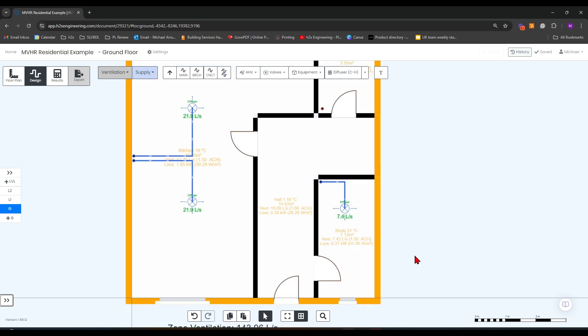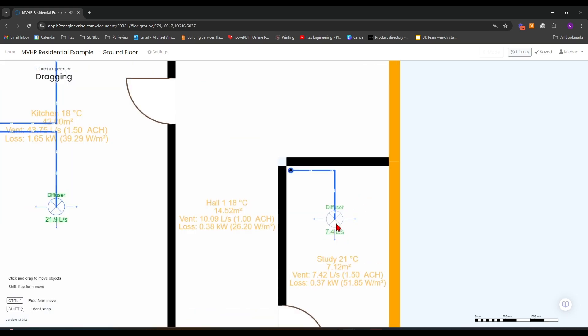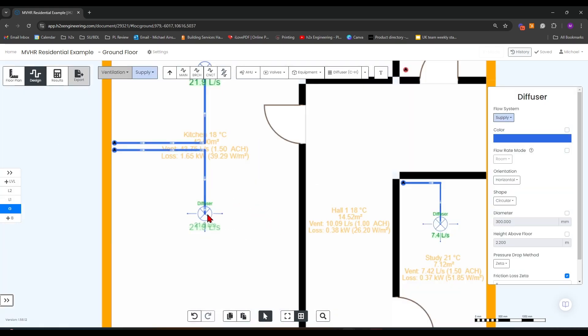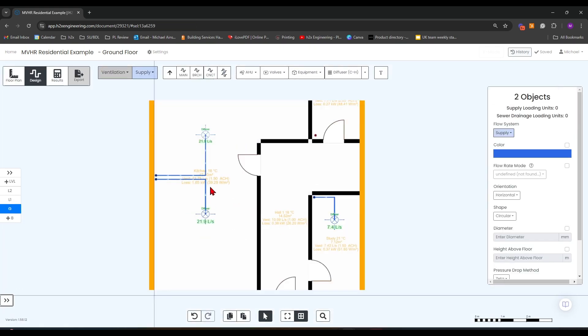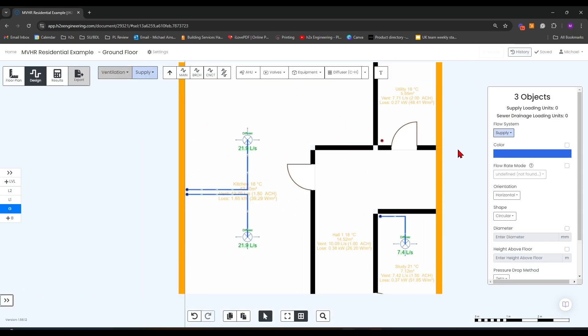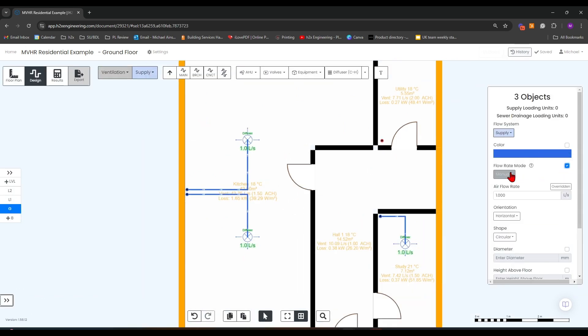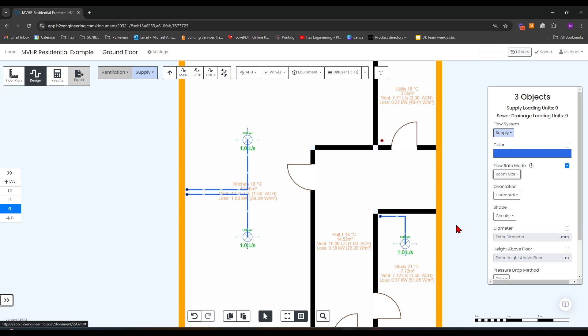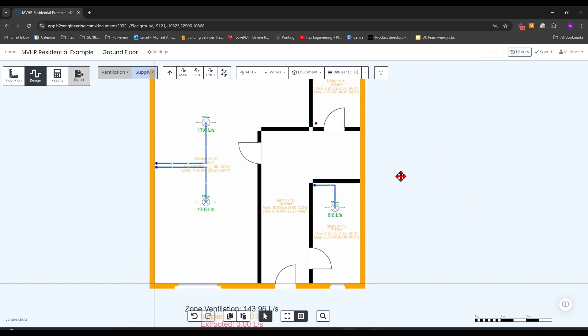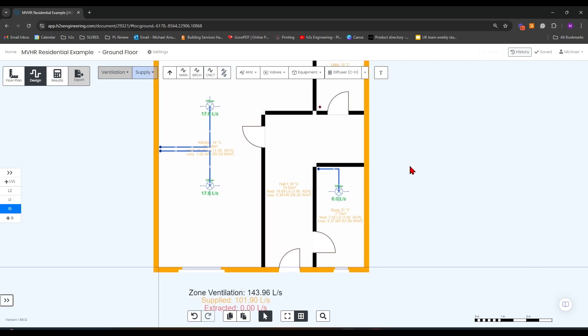You can see that even though we have added our diffusers, we aren't meeting our supplied ventilation requirement. That's because we need to set the diffuser flow rate method. So if we click on each of the diffusers holding control, we can change them all together. The method I'm going to choose is by room size.